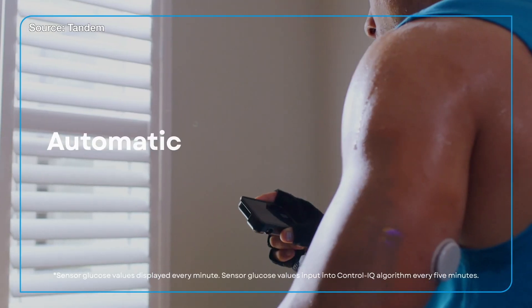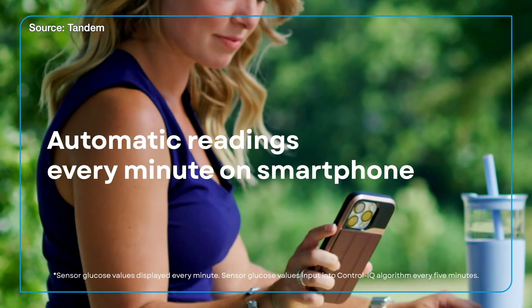Something that excites me about the Libre sensors over others is the every-minute reading. How do you think that is helping patients, having that extra four minutes of readings compared to other systems? I think the easiest thing is they can look at the screen and see it updated in real time every minute and see what direction it's moving. But the most important bit is that it allows the system to alarm potentially four minutes sooner. So if someone is going low, it'll let you know the minute they've gone low, rather than having to wait up to four minutes longer until the glucose reading updated.